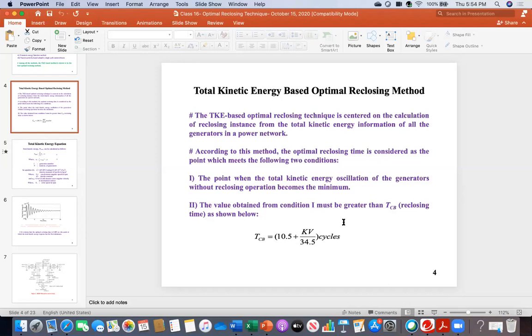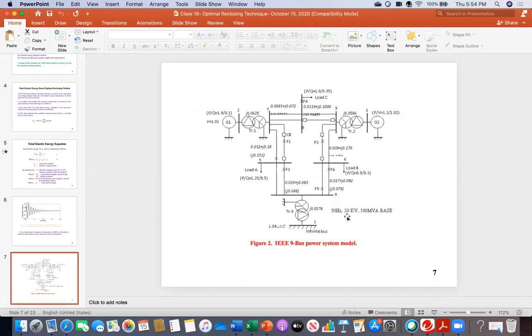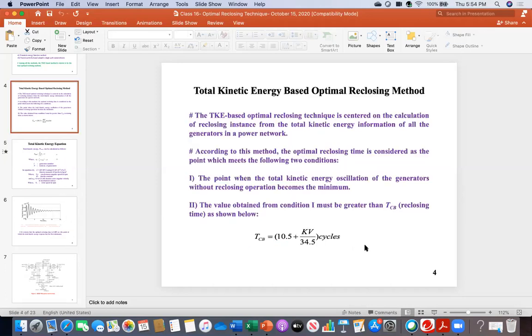This means the value obtained from condition 1 must be greater than this TCB. This means the circuit breaker closing time must be greater than this value, which is 11.07 cycles. Because this is a 50 Hertz based system, as it says 50 Hertz, the system can also be 60 Hertz, no problem. Based on the 50 Hertz system, the value of one cycle is 20 milliseconds. Time equals 1 over f. If you do 1 over 50, you get 20 milliseconds.